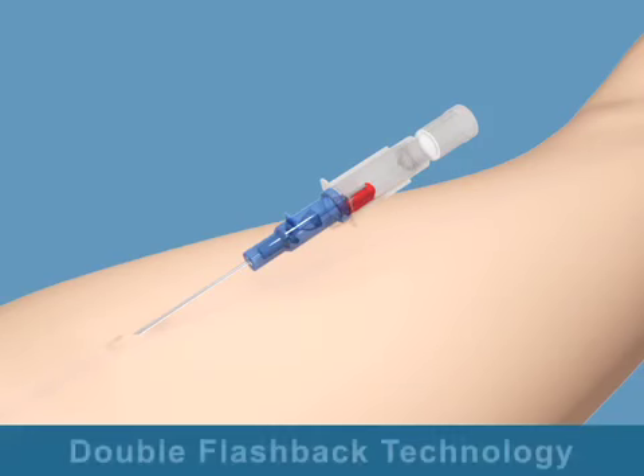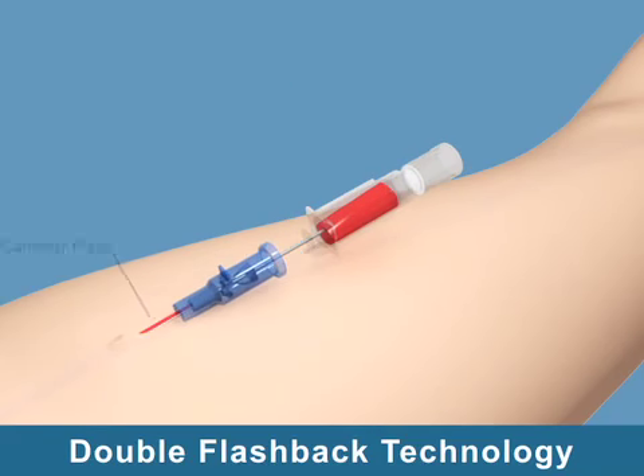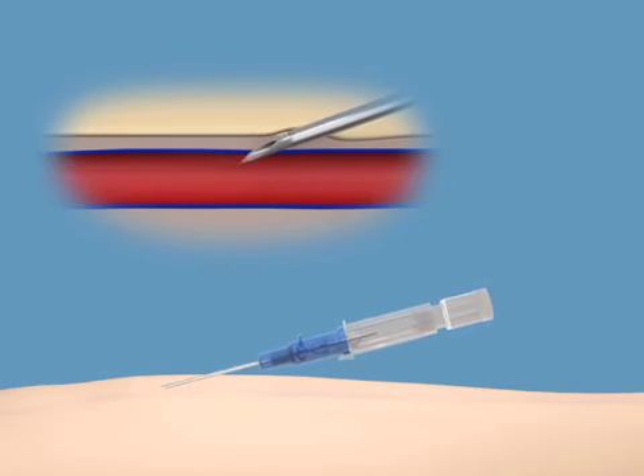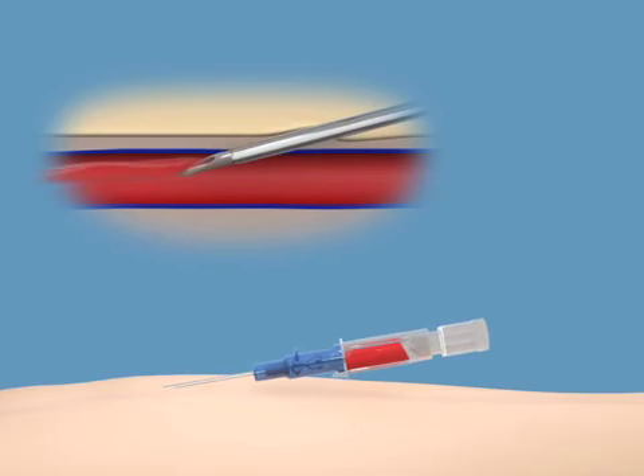Introcan Safety's double flashback technology improves first stick success through quick visualization of both the needle flash and the catheter flash. The first flashback of blood — needle flash — is visible in the clear flashback chamber, confirming the needle tip is in the vein. Using the push-off plate on the catheter hub, the catheter is advanced forward off the needle, into the vein.